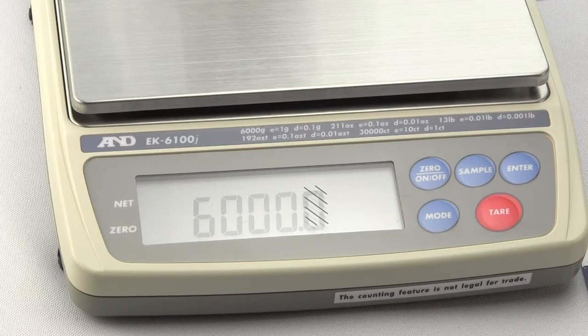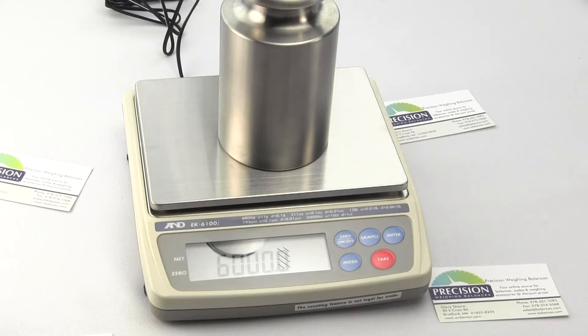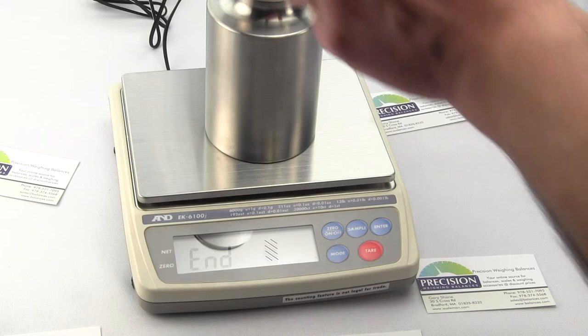So I have 4 kilograms, 2 kilograms. You place it on the weighing platform. Then you hit the ENTER key. You'll notice in the upper left-hand corner, there's a circle that says it stored the value. Then it states END.